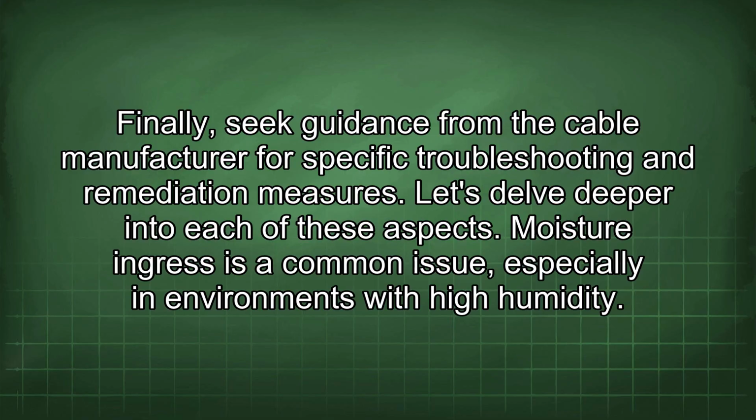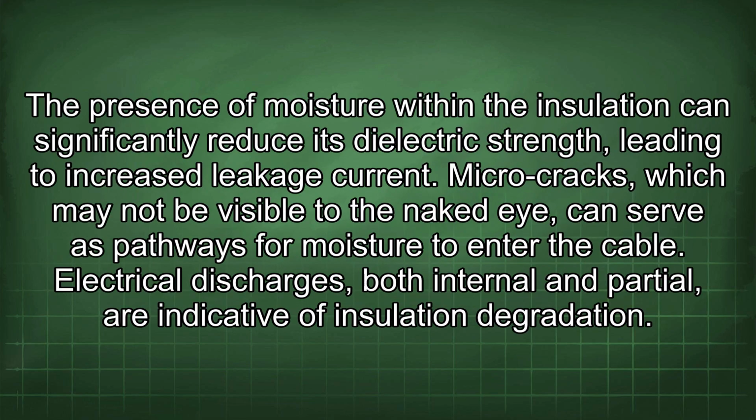Let's delve deeper into each of these aspects. Moisture ingress is a common issue, especially in environments with high humidity. The presence of moisture within the insulation can significantly reduce its dielectric strength, leading to increased leakage current. Micro cracks, which may not be visible to the naked eye, can serve as pathways for moisture to enter the cable. Electrical discharges, both internal and partial, are indicative of insulation degradation.